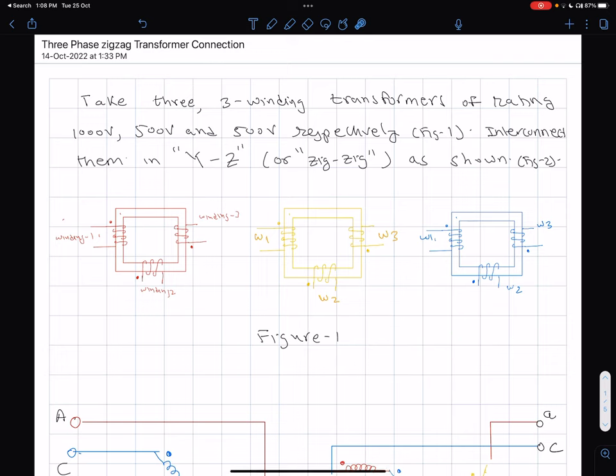But if for some reason you had a delta winding with no star-grounded generator, you could go for a zigzag connection which provides a 30-degree phase shift while also providing a ground. The intuition for needing a 30-degree phase shift is: if you have a loop in the system with a transformer that creates a 30-degree phase shift, then by symmetry any alternate path should also create a similar phase shift, otherwise circulating currents will flow under no-load conditions, unnecessarily creating losses.